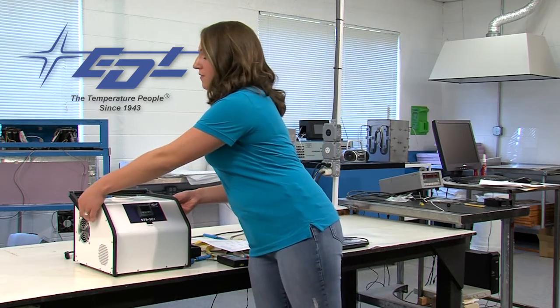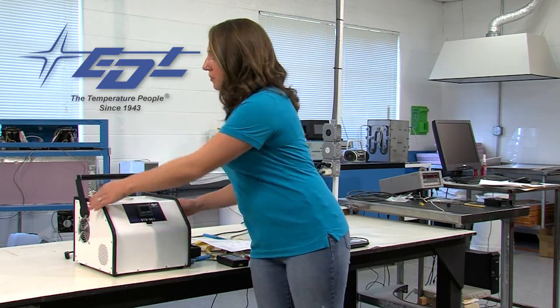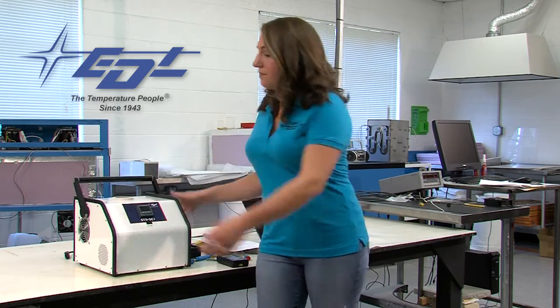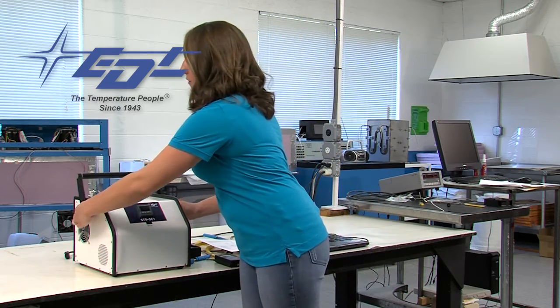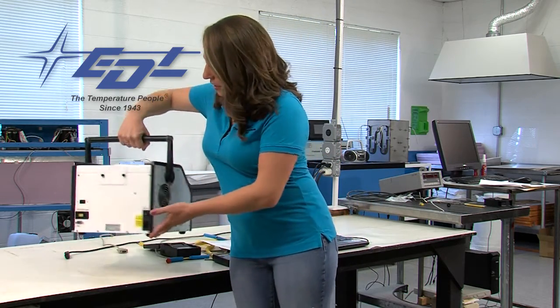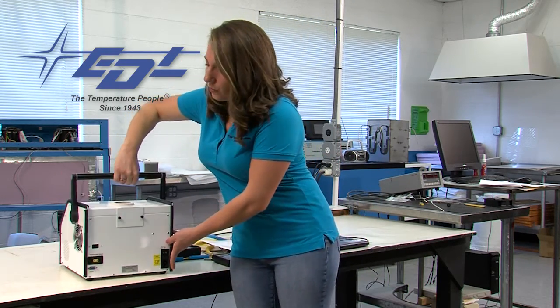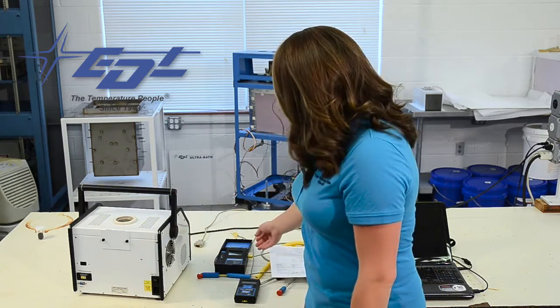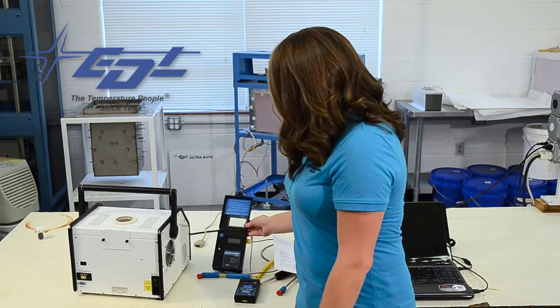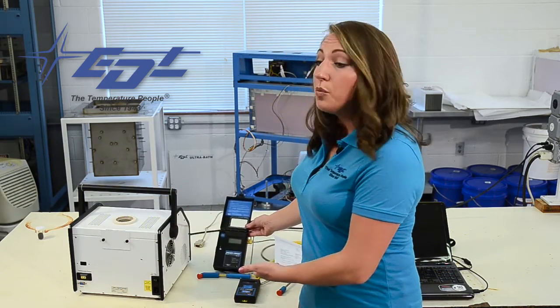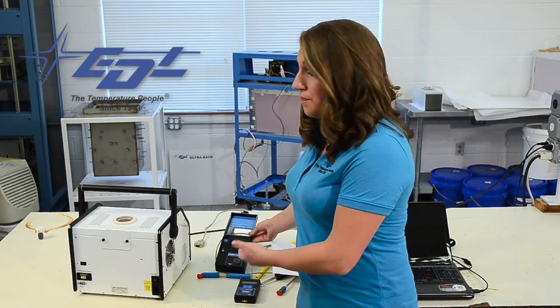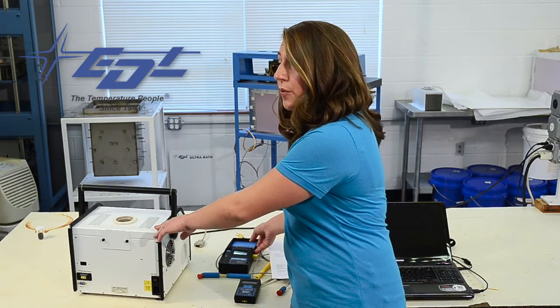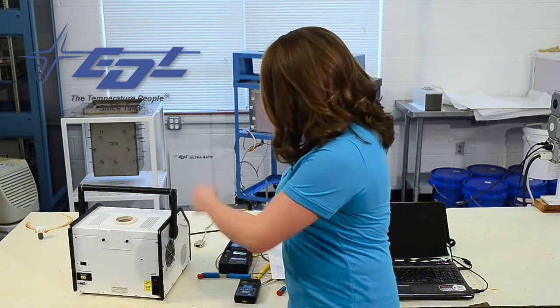Here we have an adjustable handle, helps with the portability, you can set it however you need to and on the back here we have the thermocouple output which is where I will be plugging in my reference system which is the pocket probe that the STS Calibrator Reference System comes with.